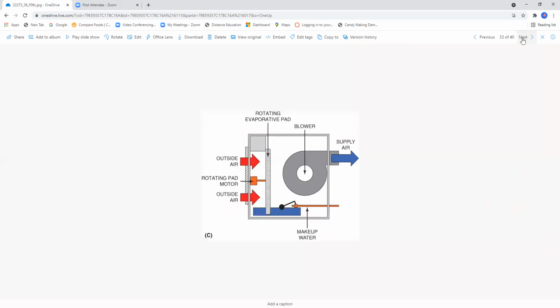This illustration is also located on the same page 1064, and this is a rotating element. I've worked on a lot of these when I worked at Mount Sac Community College many years ago. The shop buildings utilized this technology in order to cool the shop areas. You had a motor that operated at a slow RPM. You had a water trough, which was constructed of stainless steel. You had a water makeup, and basically the water would make up into this tank, and this wheel would spin at a slow speed and pick up the water droplets.